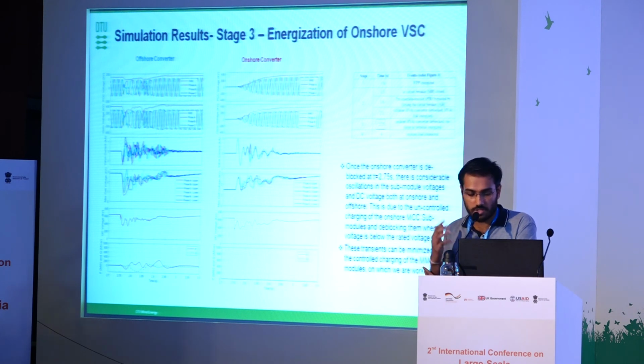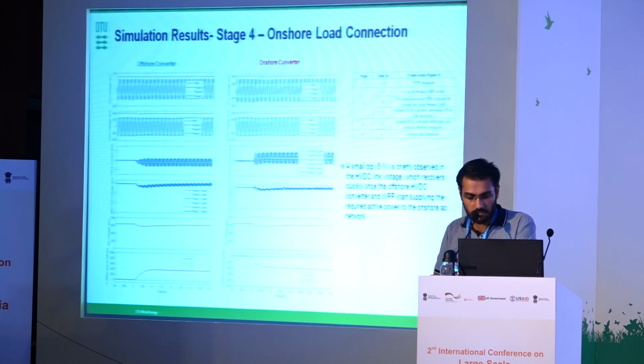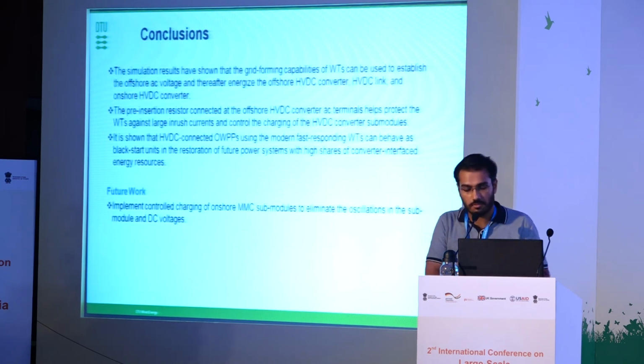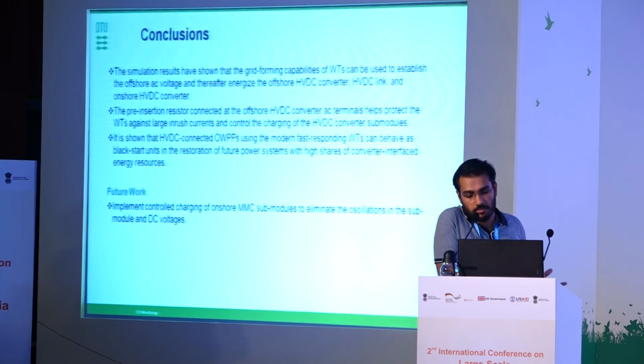However, right now it is just uncontrolled, but ultimately it does reach steady state, and then the onshore voltage starts to be formed. At 4 seconds we pick up an example passive load, and there is an HVDC link voltage drop, but once the wind power plant power starts reaching the onshore side, the transient disappears. So in conclusion, with grid forming capabilities, wind turbines can be used to form the offshore collector island, energize the HVDC link, and ultimately provide block load picking up capability.